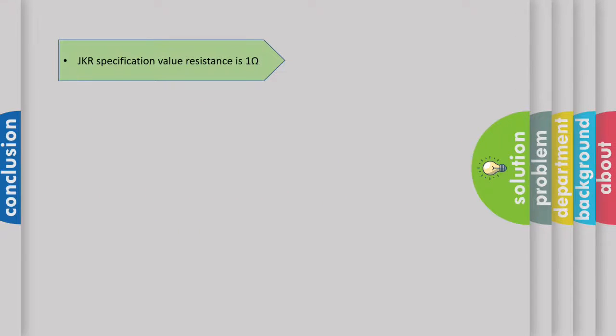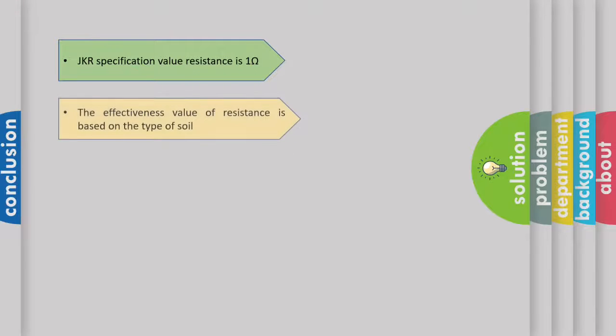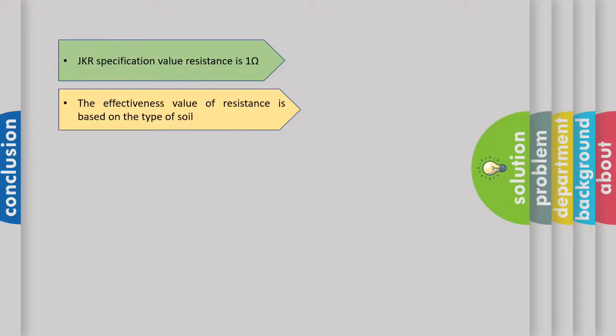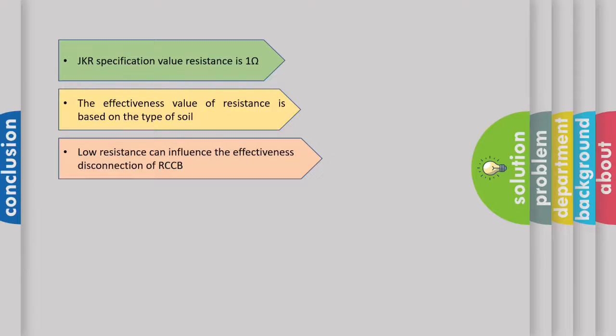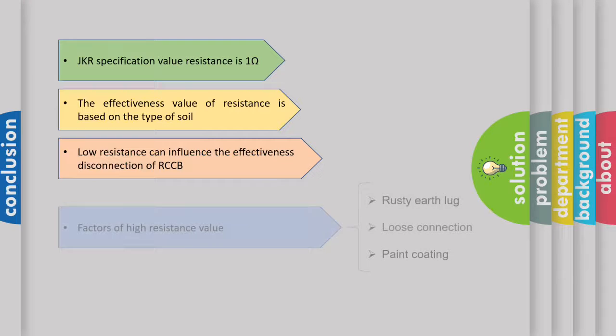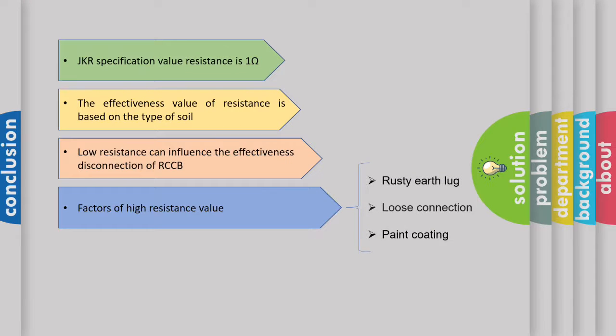Basically, JKR specification of the value of earth resistance is below 1 ohm. It is actually hard to get that value since the effectiveness of the resistance based on the type of soil. The lowest resistance can influence the faster disconnection of RCCB. Sometimes, the value of earth resistance is high because of the factors such as rusty earth lug, loose connection, and paint coating.